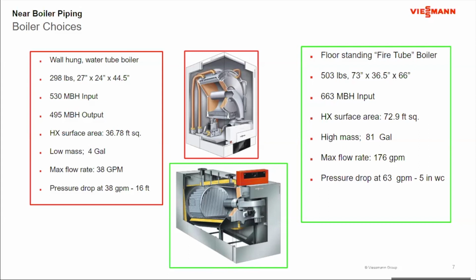Now, when we look at the application of these boilers from a near-boiler standpoint, there are a few things we need to look at, and this discussion kind of works out whether a boiler should be utilized as a primary-secondary install, or possibly is this a better boiler to go with a direct connect, a variable primary installation.